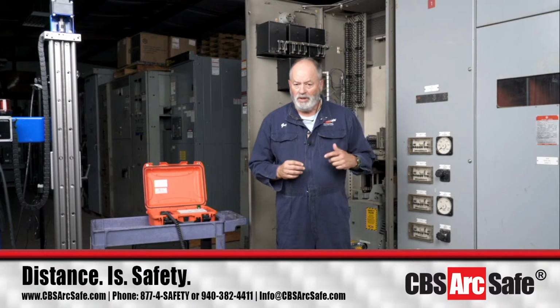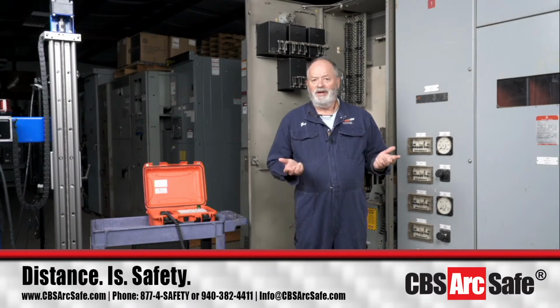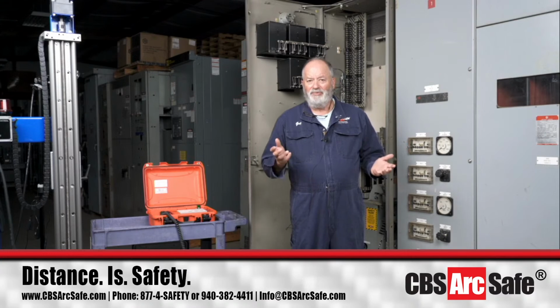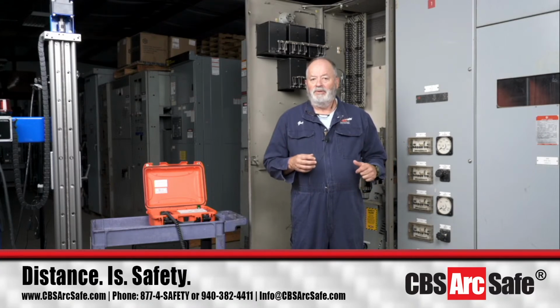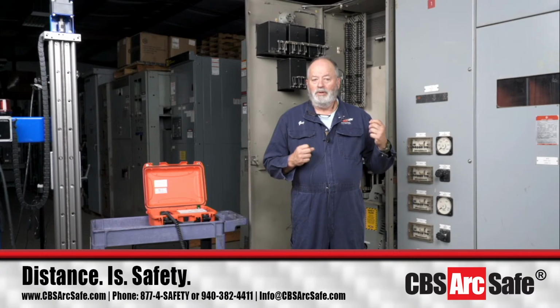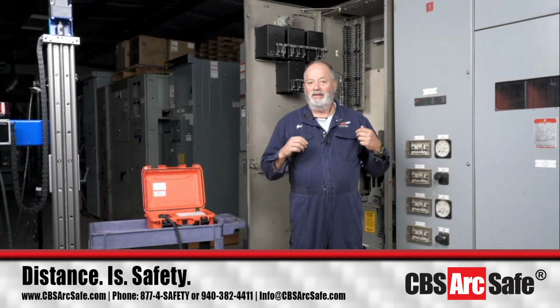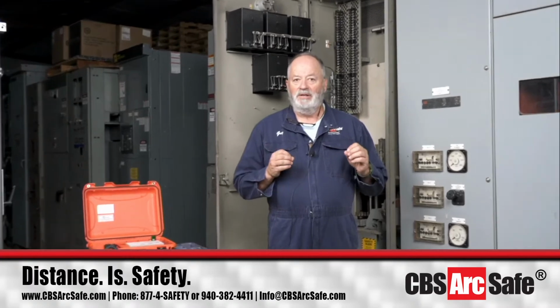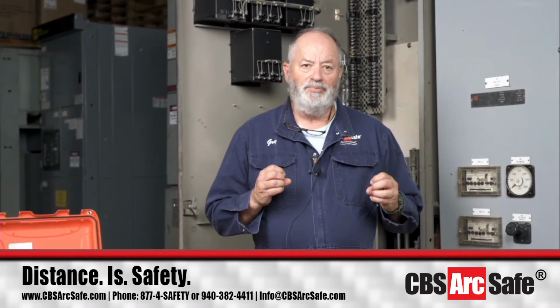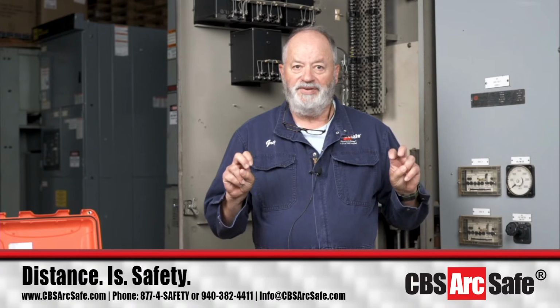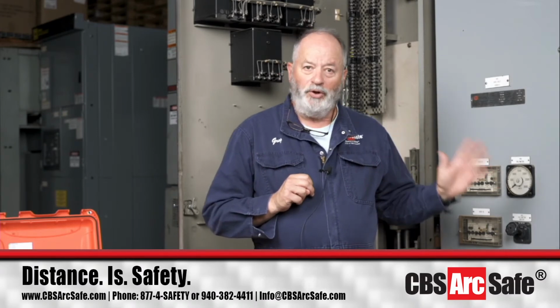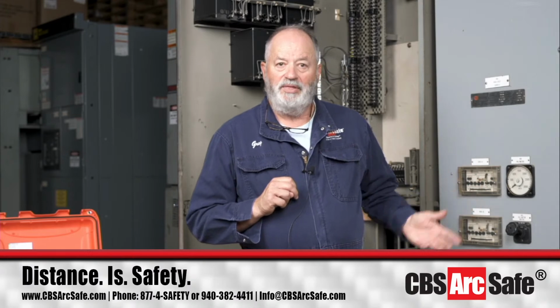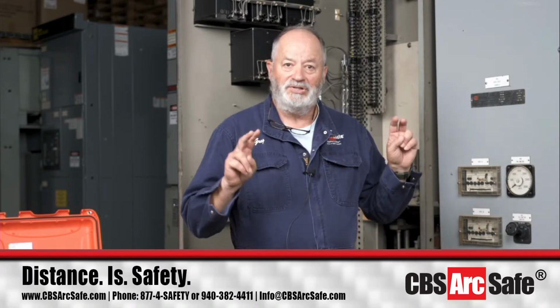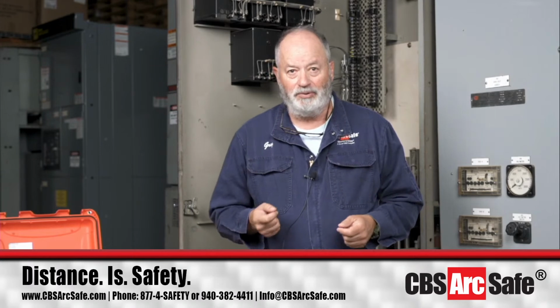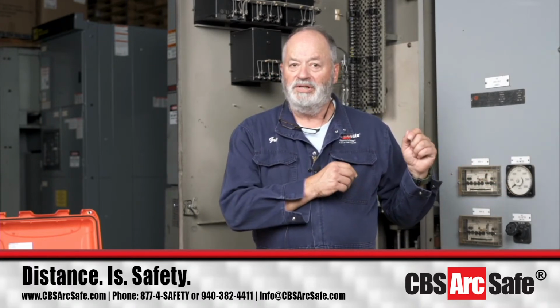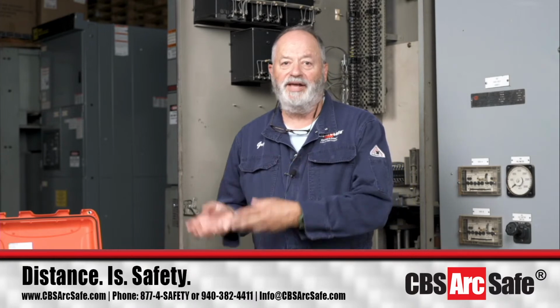Okay. The Magne-Blast switchgear started first in around the circa 1950 range, and the breakers were first made by General Electric, and then in about the late 1970s, General Electric put their first vacuum version in what was called a VVC. And you can find oil breakers in some locations that are equipped to go into a Magne-Blast M26, M36 style cubicle. So you could have an oil breaker in one of these things, you can have an air breaker in one of these things, you can have a vacuum breaker.